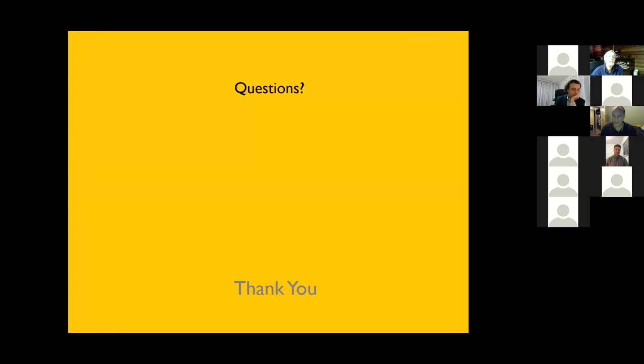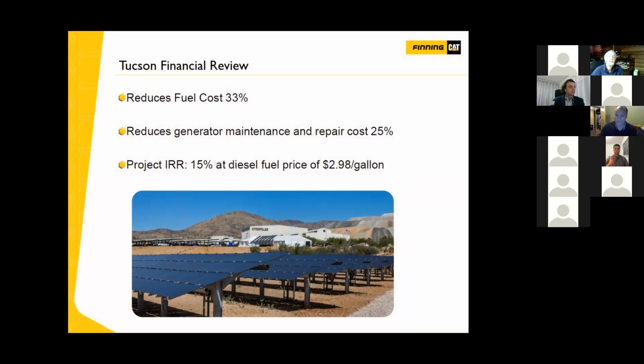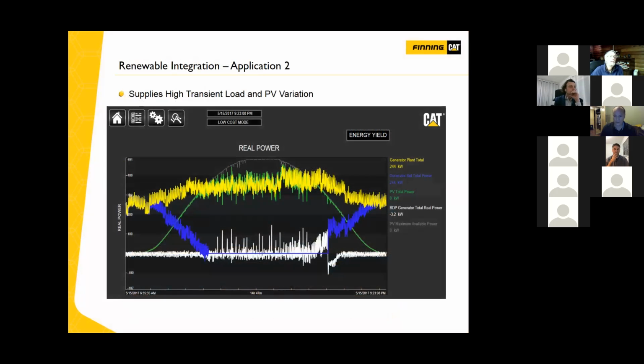When the microgrid controller powers down the photovoltaics, does that need to be configured, or is that basically out-of-the-box functionality? It is out of the box, assuming the inverters, existing or newly installed, have the ability to take that command, since the master microcontroller sends the command through communications to the specific PV inverter or inverters telling them to dial back. As long as they have the smarts for PV curtailment, which most of them do, they will react to the MMC.